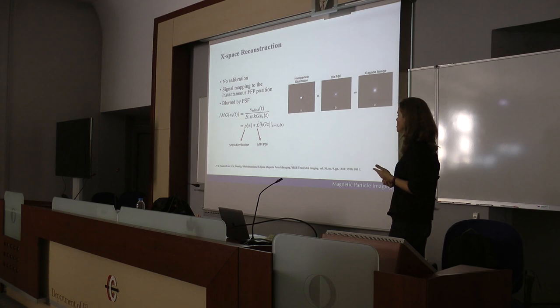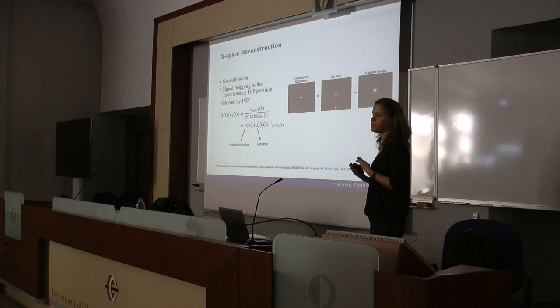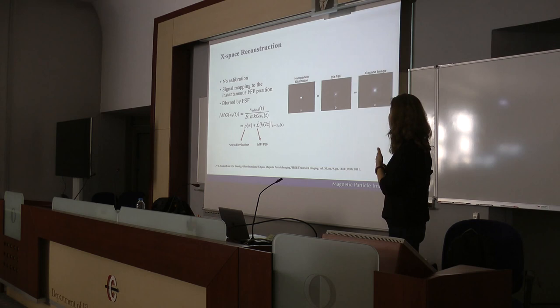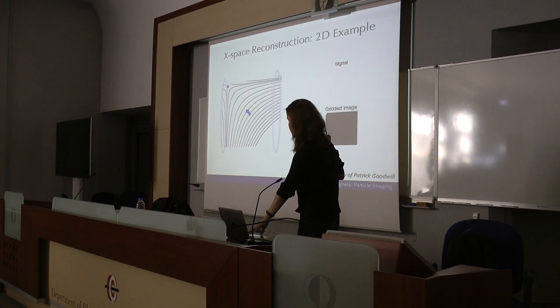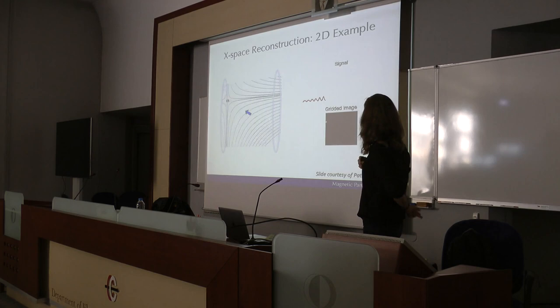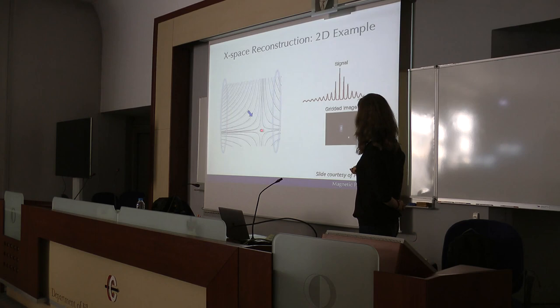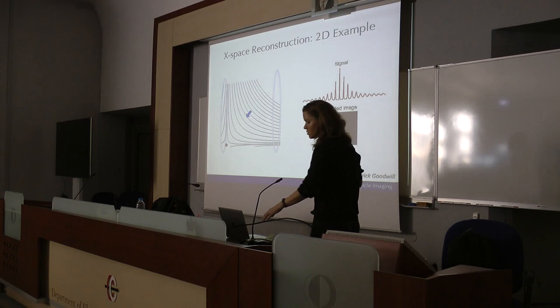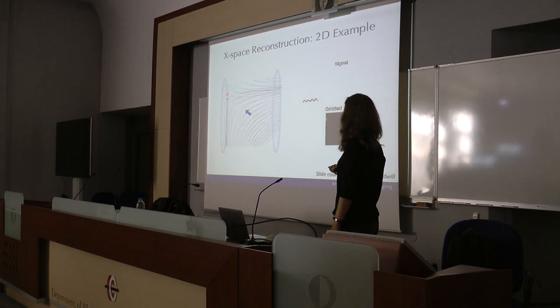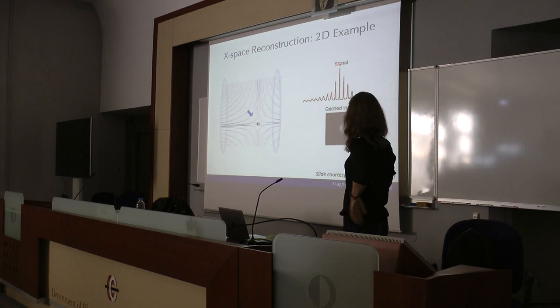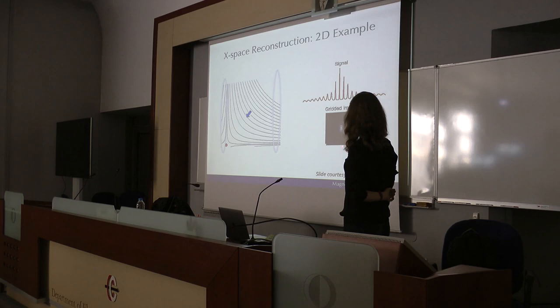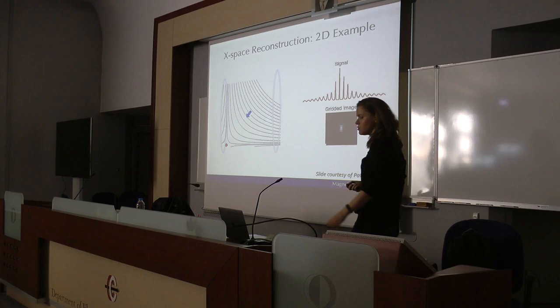Comparing x-space to system function reconstruction: system function reconstruction performs deconvolution and accounts for all system response, whereas in x-space it is integrated into the image — though further processing can improve resolution. In the x-space demonstration, the field-free point is swept in space. As the field-free point changes location, the nanoparticle aligns back and forth and generates an MPI signal. Knowing the position of the field-free point, the signal is gridded in space to produce a blurred version of the nanoparticle distribution as the MPI image.